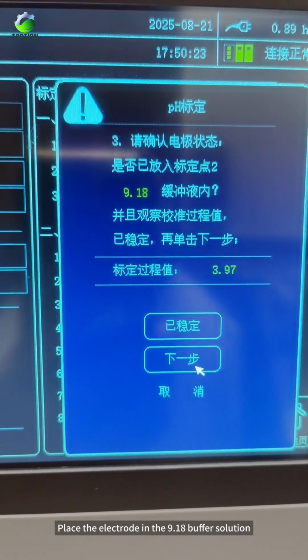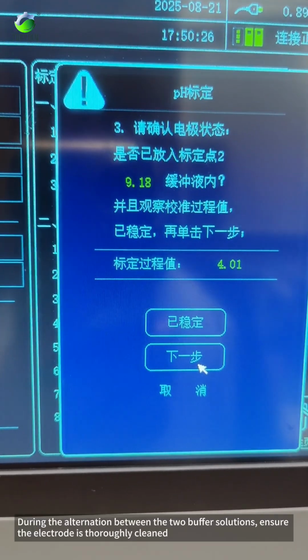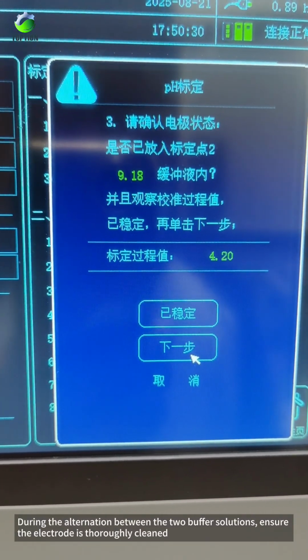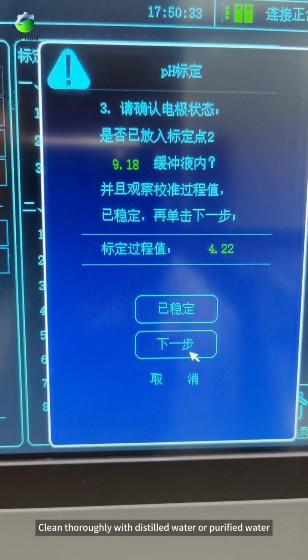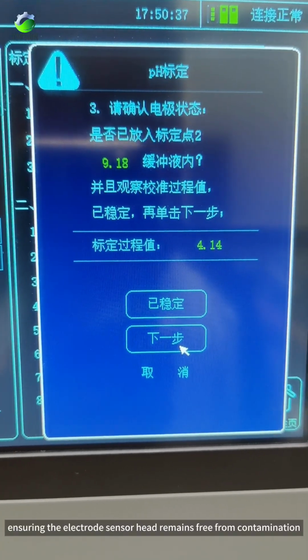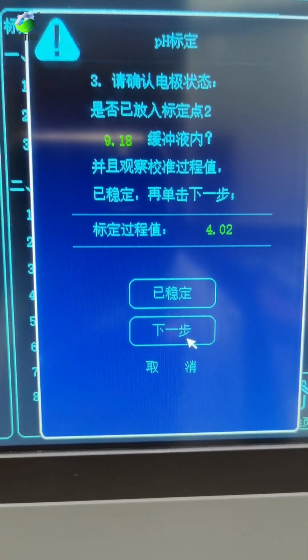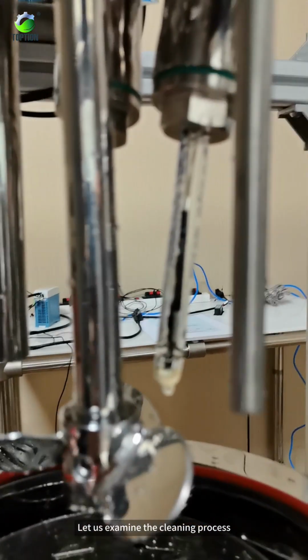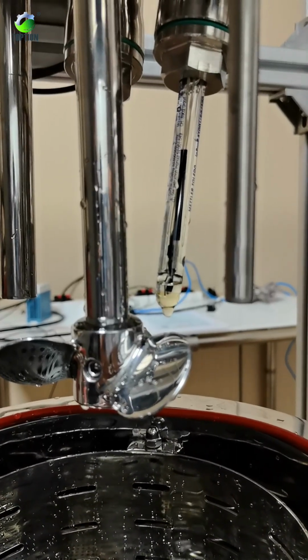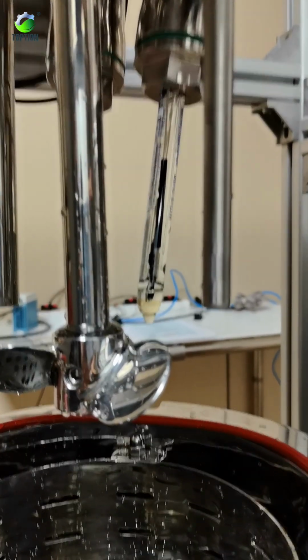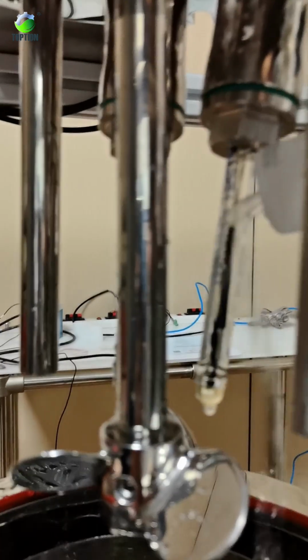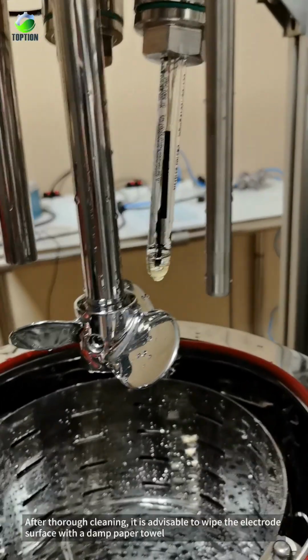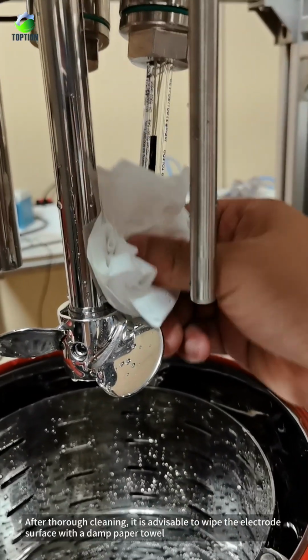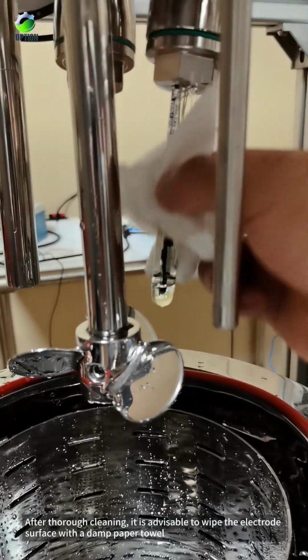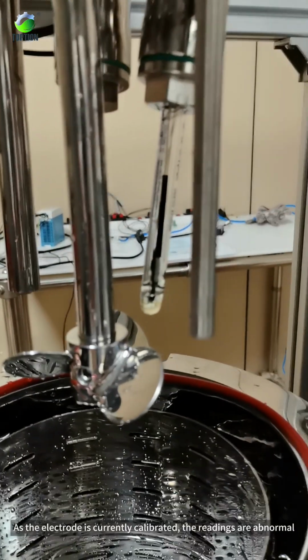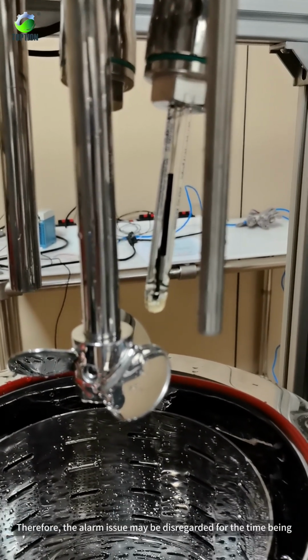Place the electrode in the 9.18 buffer solution. During the alternation between the 2 buffer solutions, ensure the electrode is thoroughly cleaned. Clean thoroughly with distilled water or purified water, ensuring the electrode sensor head remains free from contamination. Let us examine the cleaning process. After thorough cleaning, it is advisable to wipe the electrode surface with a damp paper towel. As the electrode is currently being calibrated, the readings are abnormal. Therefore, the alarm issue may be disregarded for the time being.